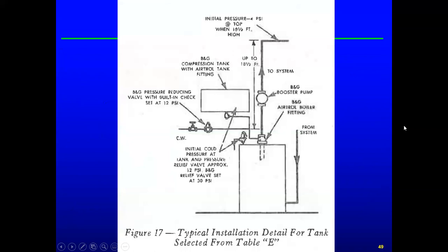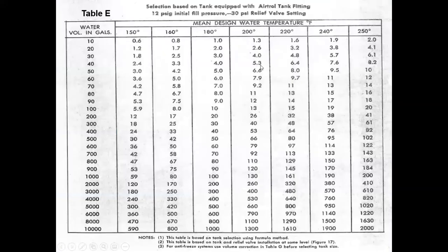I put this system diagram in here because we went through this before, the elevation change, and came up with the 12 PSIG down here at our cold water coming in, that's our pressure reducing valve that sets the 12 here. All this kind of ties in together at about the same elevation. So we're going to have 12 in here and all this. Here's our pump, and we'll talk later, this becomes our point of no pressure change relative to pump operation and all this. But this is kind of a picture of the standard setup. So we got 12 PSIG and we can go to 30.